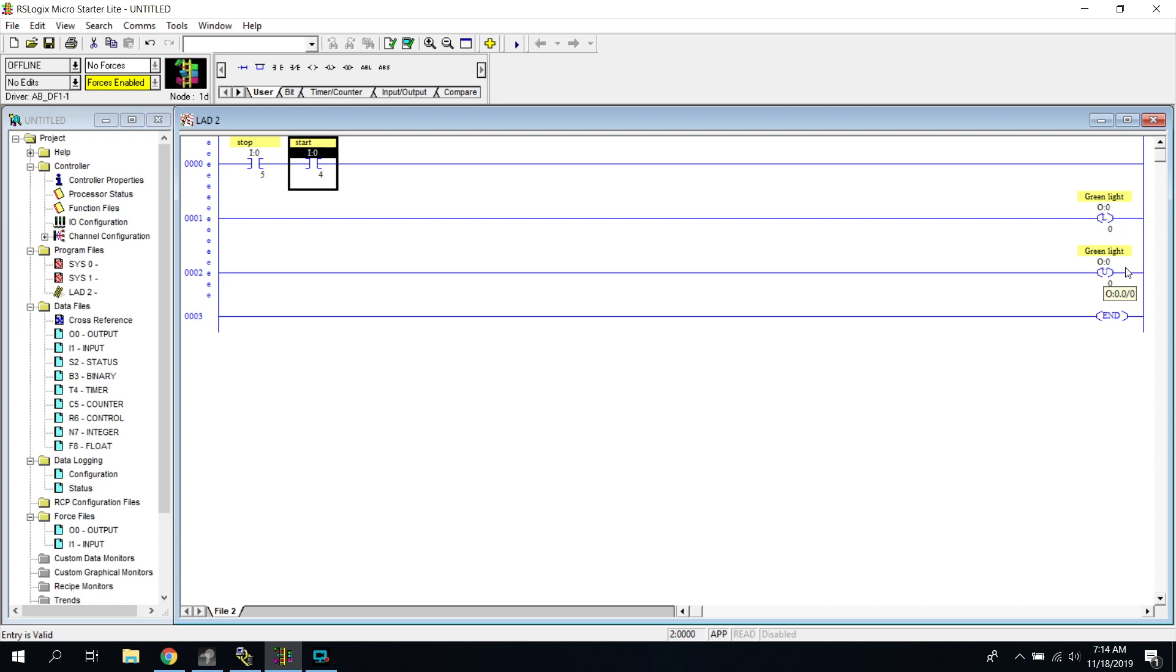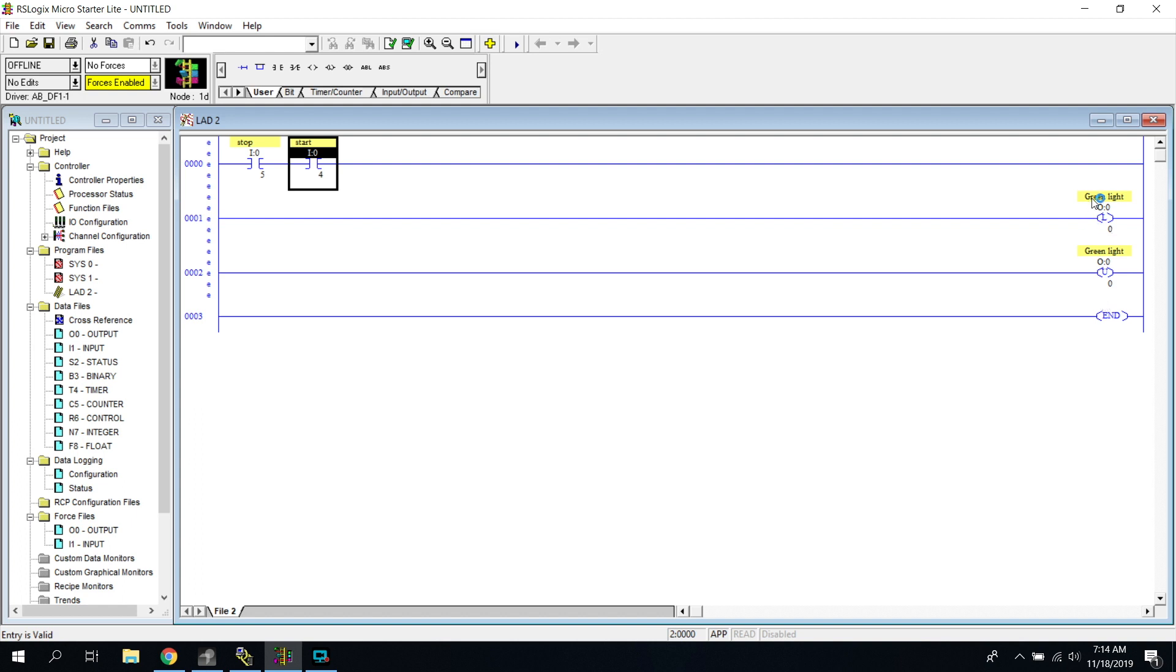Notice that there are two of them, meaning there's two output instructions that have the same address, which was a big no-no if you remember back in the beginning of this class. We talked about how you can't have more than one output that is addressed the same. It confuses the computer, and this one does have its issues, but you have to because the one output right here is going to latch this light on and this one right here is going to unlatch that light. So it's going to turn the light off.